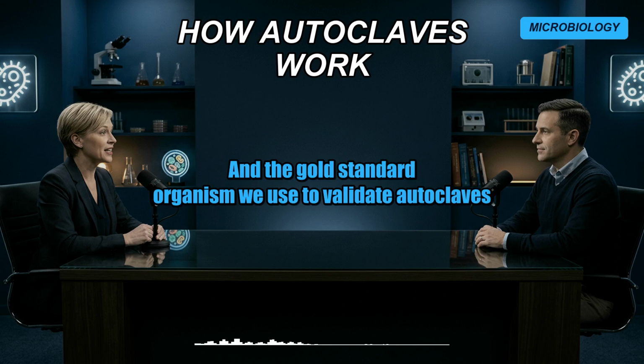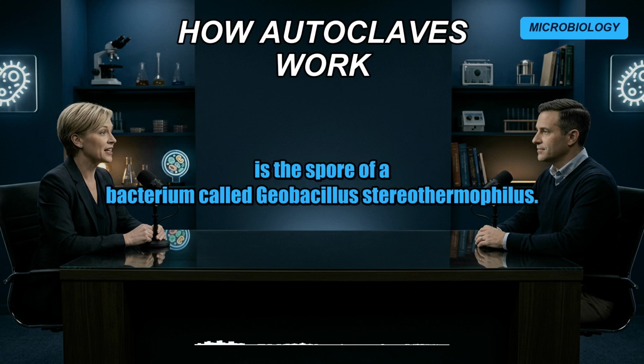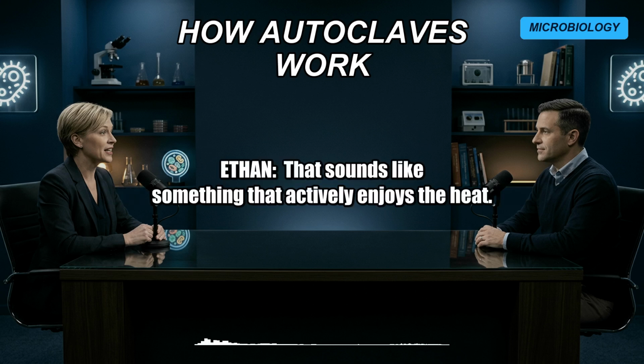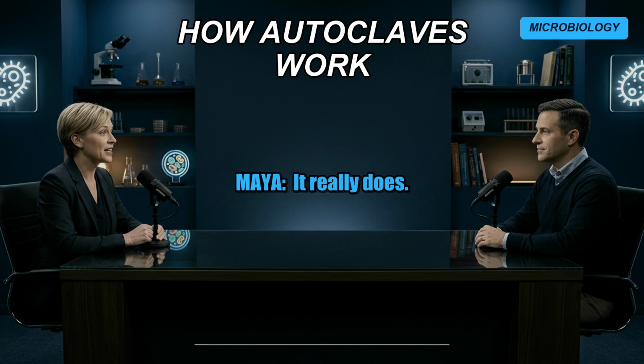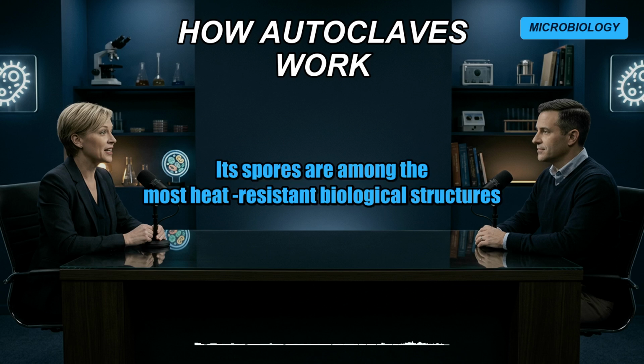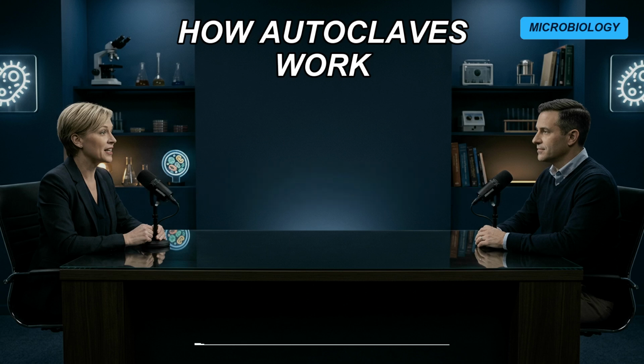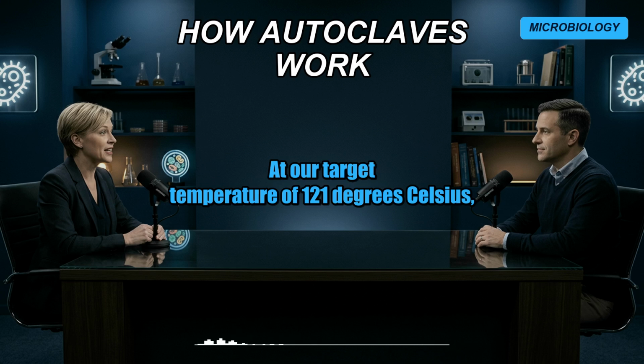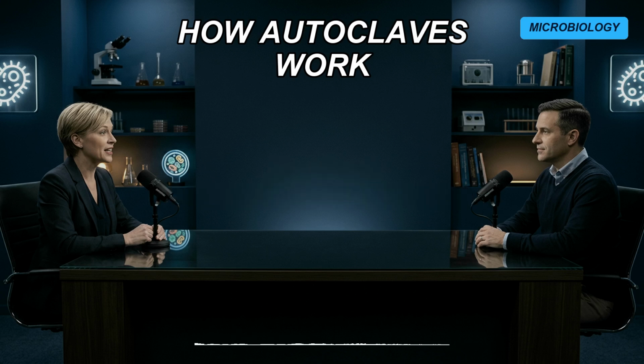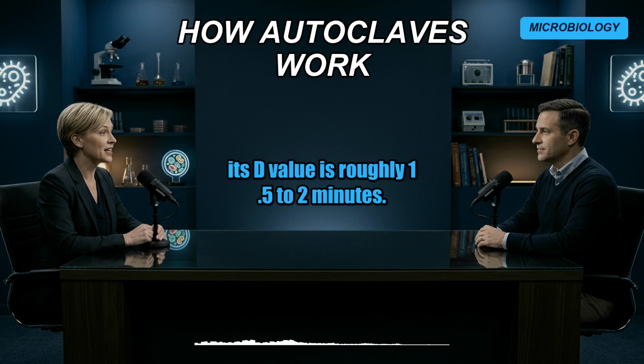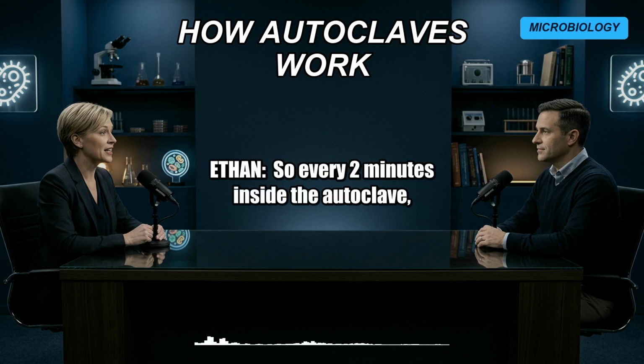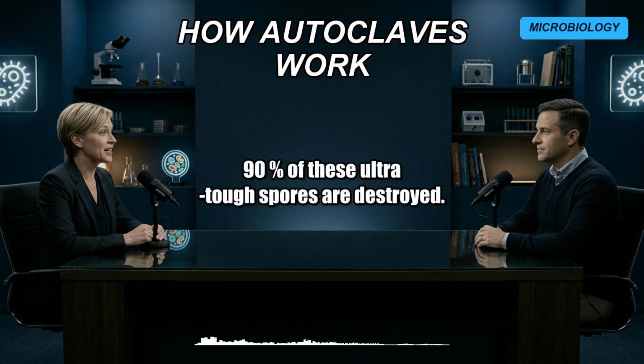And the gold standard organism we use to validate autoclaves is the spore of a bacterium called Geobacillus stearothermophilus. That sounds like something that actively enjoys the heat. It really does. It's a thermophile. Its spores are among the most heat-resistant biological structures we know of. At our target temperature of 121 degrees Celsius, its D value is roughly 1.5 to 2 minutes. So every 2 minutes inside the autoclave, 90% of these ultra-tough spores are destroyed.